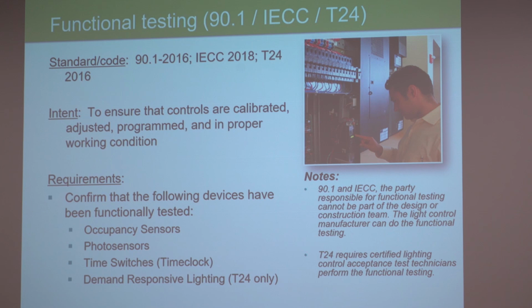Okay, so now that we have all these mandatory lighting control requirements in the codes, there's now requirements to have them functionally tested to make sure they are installed and going to be used as intended. So IECC and ASHRAE and California Title 24 require that occupant sensors, daylight sensors or photo sensors, time clocks, time switches, and daylight responsive control, demand responsive controls for California be functionally tested.